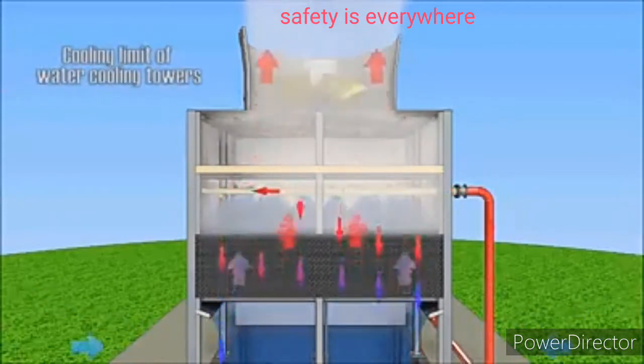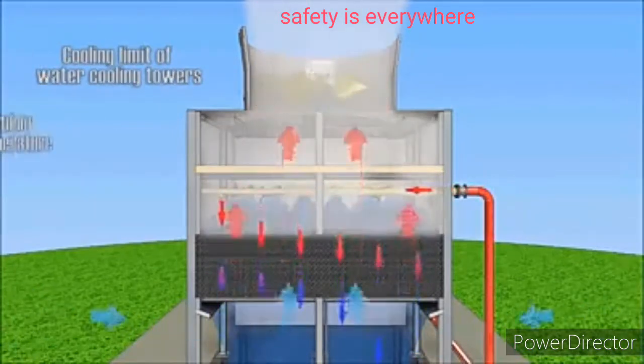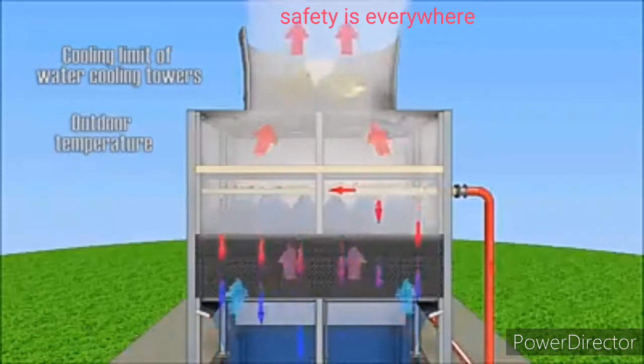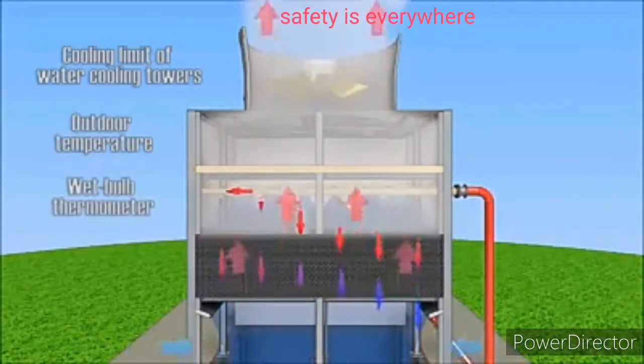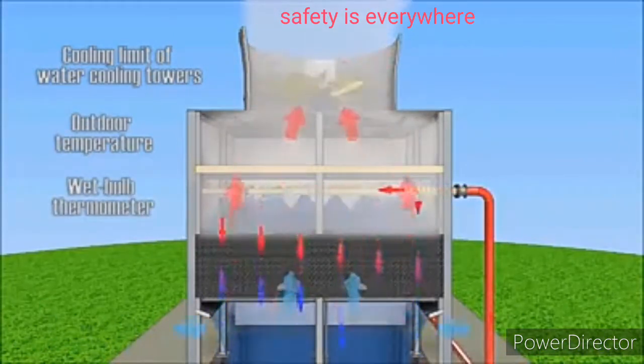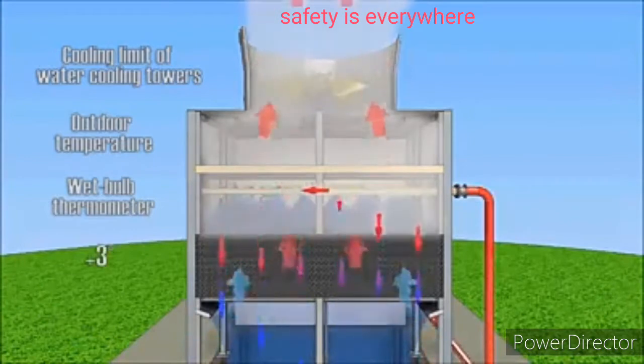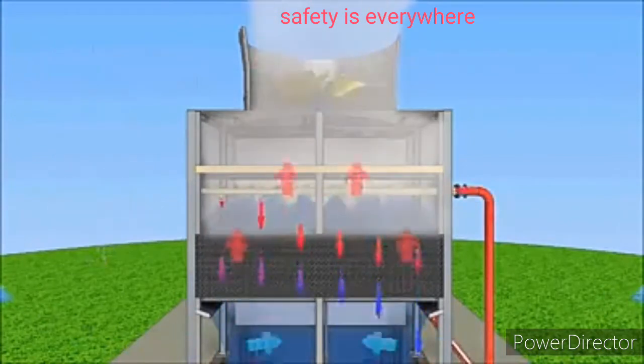The limit of the cooling of water in the cooling tower is the temperature of the outside air, the wet bulb temperature. In practice, the limit of cooling is the wet bulb temperature plus 3°C.